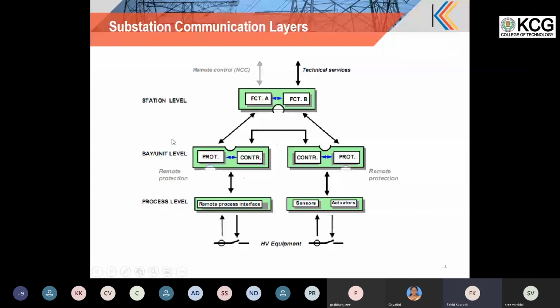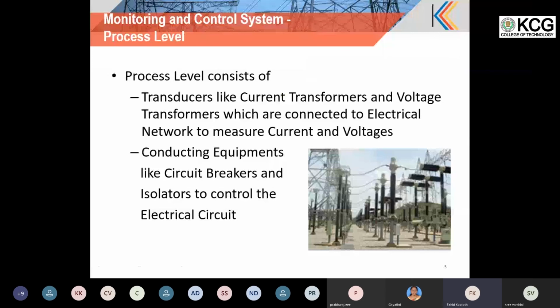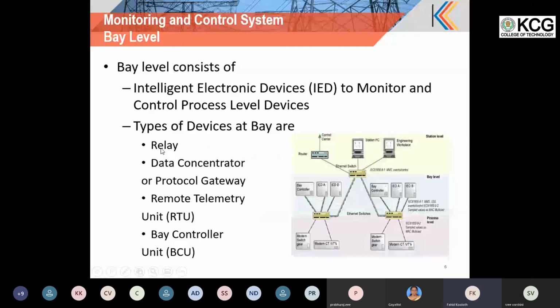Then moving on to details of the process level. The process level consists of current transformers and voltage transformers, which are used to measure current and voltages, and switching equipment like circuit breakers and isolators to control the flow of the current. Then the bay level consists of relays; multiple vendor relays will be there at the bay, data concentrators or protocol gateways will be there, remote terminal units or RTUs will be there, and bay controllers will be there at the bay level.